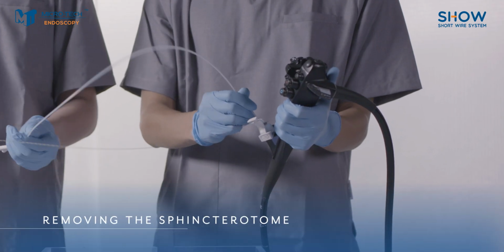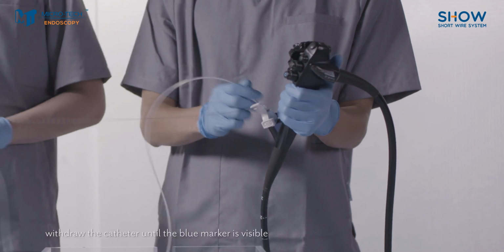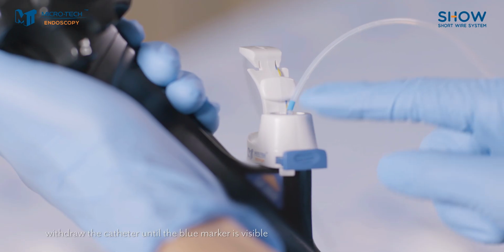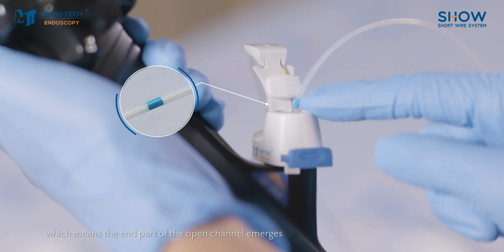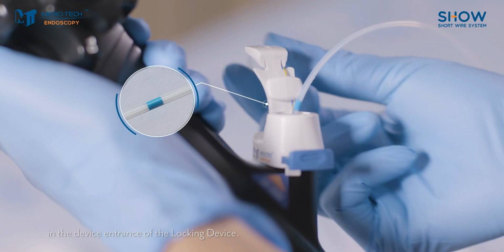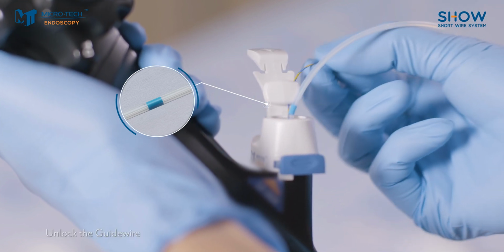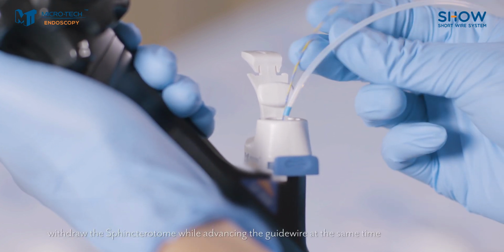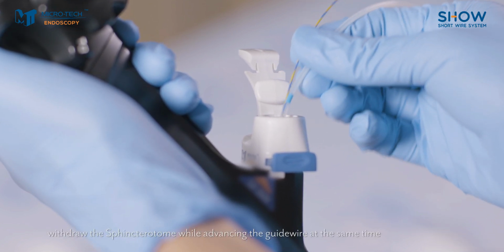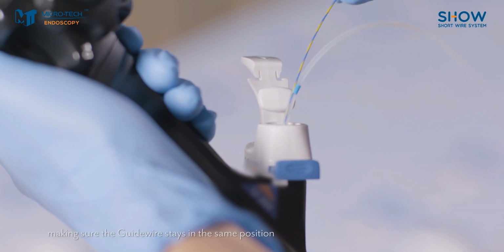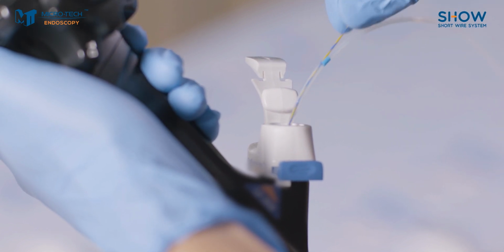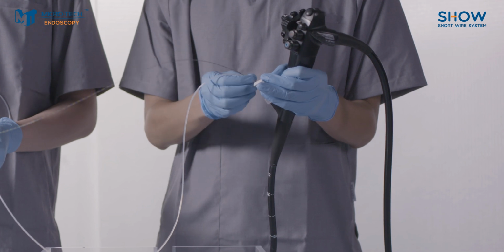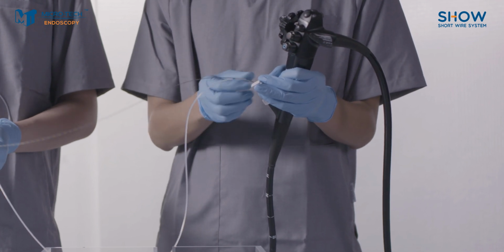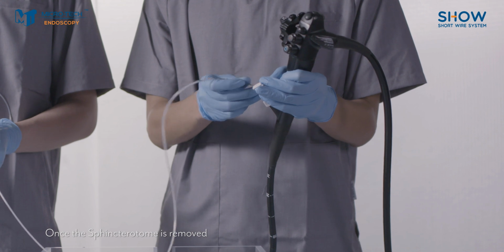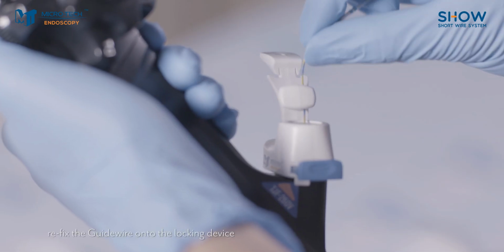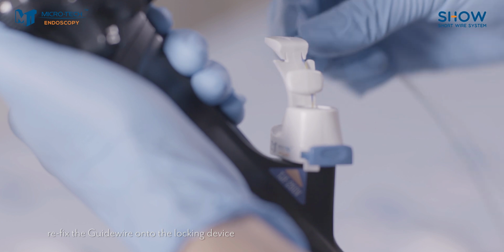Removing the sphincterotome. To remove the sphincterotome, withdraw the catheter until the blue marker is visible, which means the end part of the open channel emerges in the device entrance of the locking device. Unlock the guide wire. Withdraw the sphincterotome while advancing the guide wire at the same time, making sure the guide wire stays in the same position. Once the sphincterotome is removed, refix the guide wire onto the locking device.